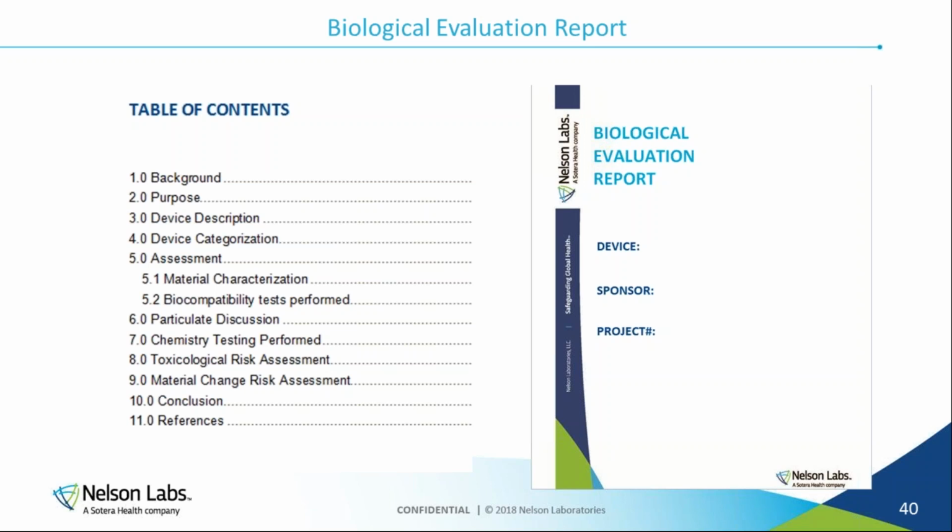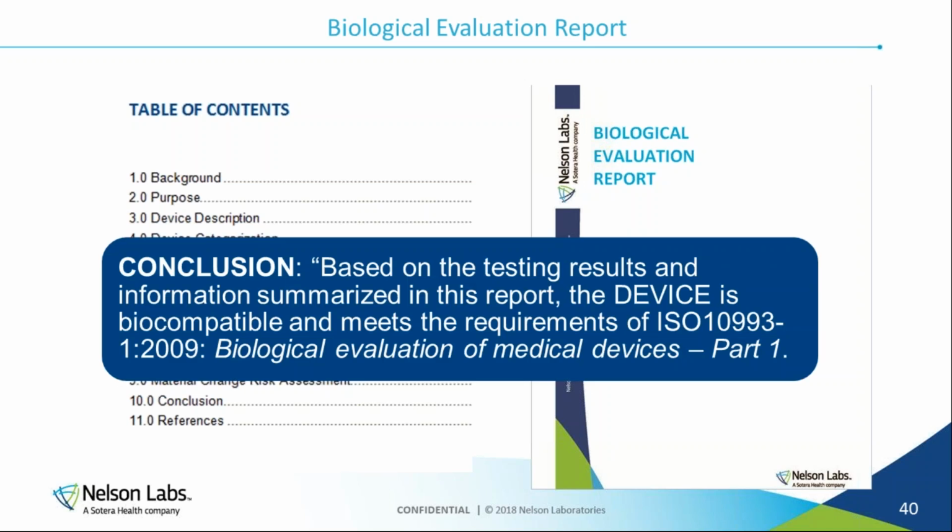This goes over very well for the agencies so they can see everything up front. When we see clients who submit just their test reports and there's no initial conversation, no final conversation to address the test results and what was found, there's a lot more questions and a lot longer time to get their product through to market. So this really saves a lot of time. And the conclusion for a biological evaluation report is hopefully that it meets the requirements of ISO 10993 Part 1 and can be considered safe and no additional testing is needed.